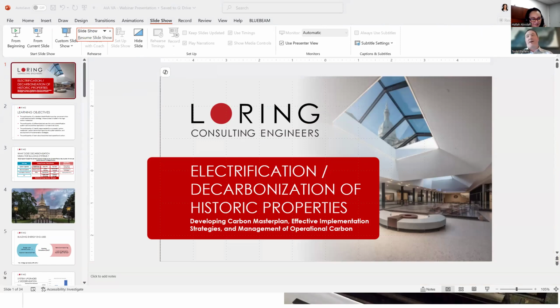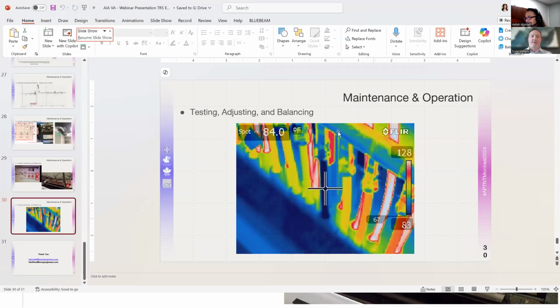So we had to bring in the balancer just to check each of the circuits independently from the main header flow rate sensors. Yeah, this is the image, right? You can see the circuits that were working properly are lit up bright white and red. But the one in the crosshairs is a circuit that is stone cold. It's at the bottom end of that temperature gradient, so it's not getting sufficient flow. The balancer came in and was able to make sure that we got sufficient flow not only in that one circuit, but in all of the circuits, to keep it balanced.